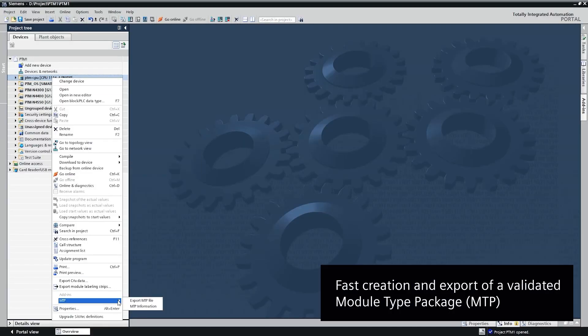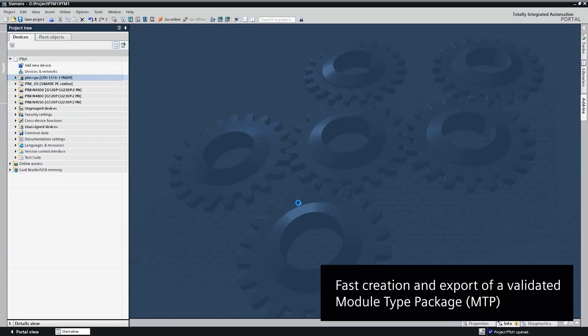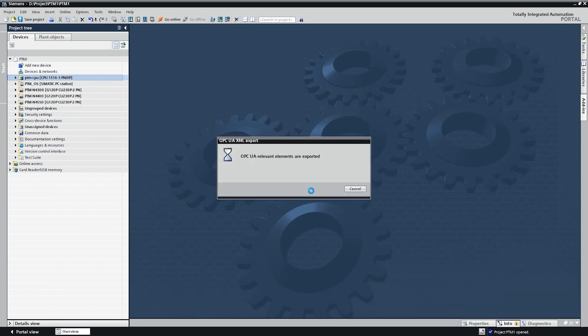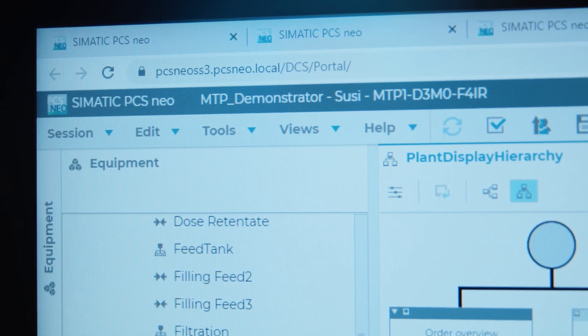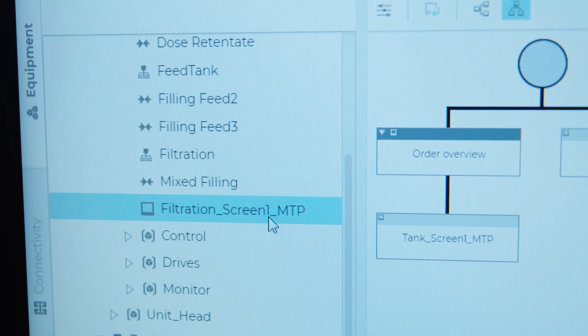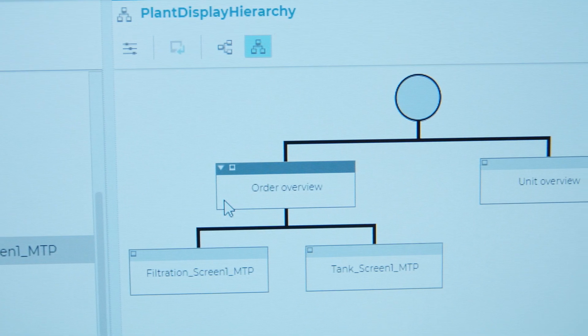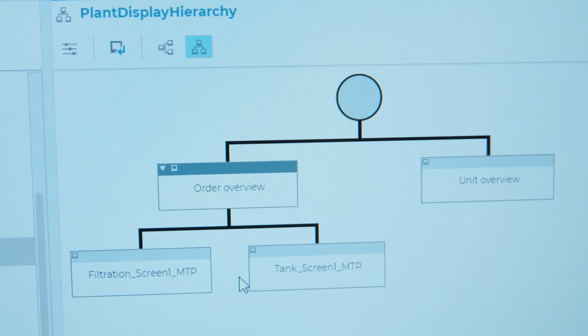After programming, the Simatic MTP creator generates the MTP file from the TIA Portal projects with only one click. The orchestration of the modules and the backbone is implemented in the process orchestration layer Simatic PCS Neo. Here, the MTP files of the individual modules are imported and managed as templates in the library. These templates are then instantiated according to the plant's physical hierarchy.